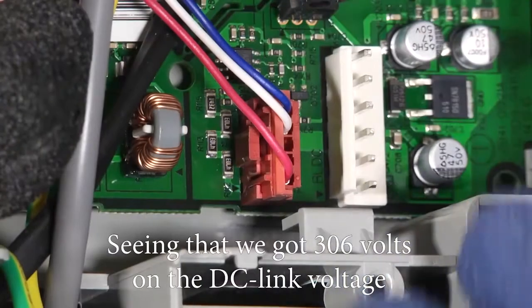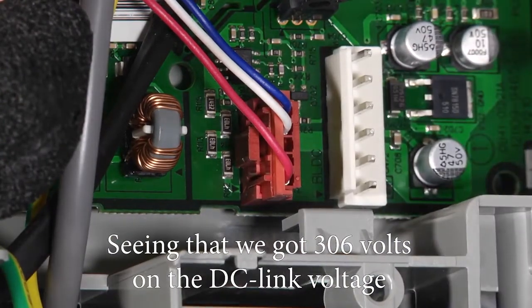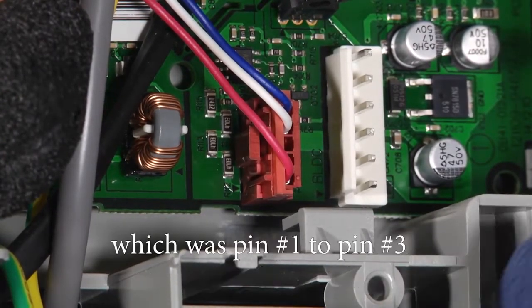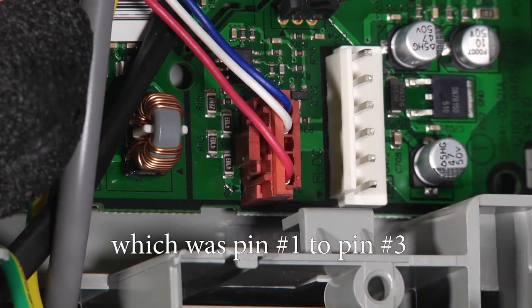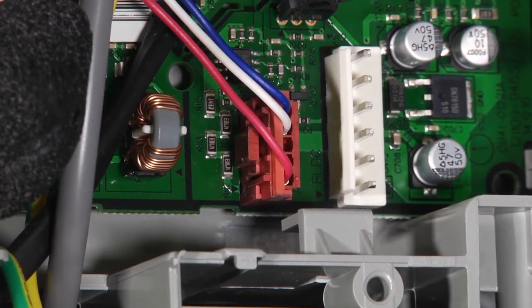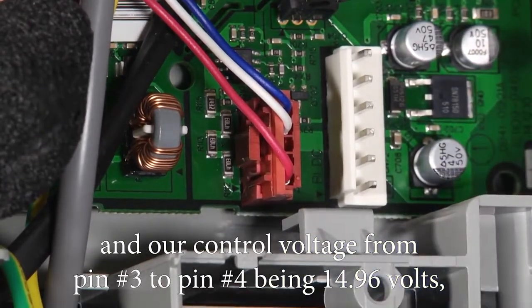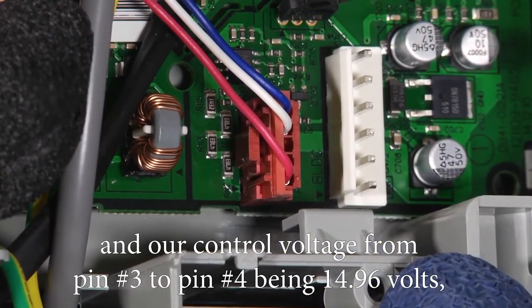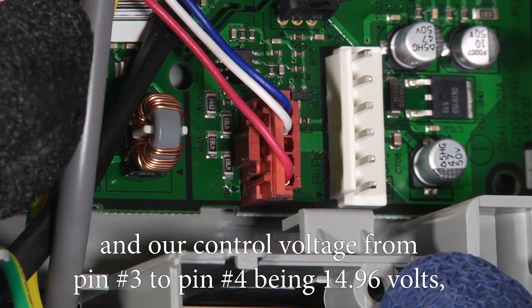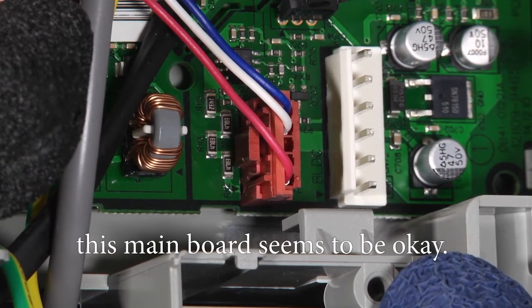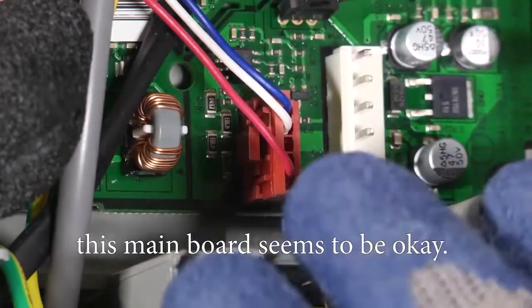Seeing that we got 306 volts on the DC link voltage, which was pin number one to pin number three, and our control voltage from pin number three to pin number four being 14.96 volts, this main board seems to be okay.